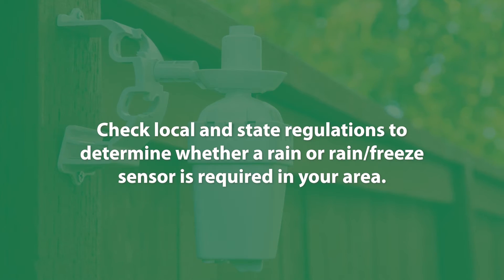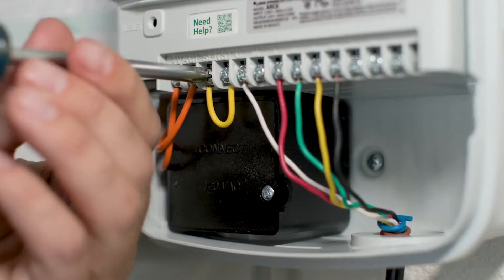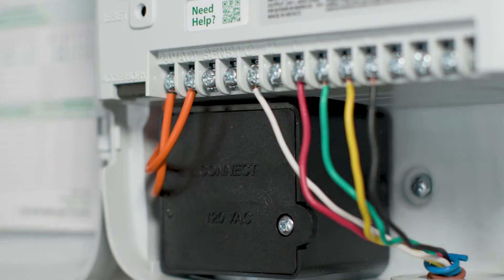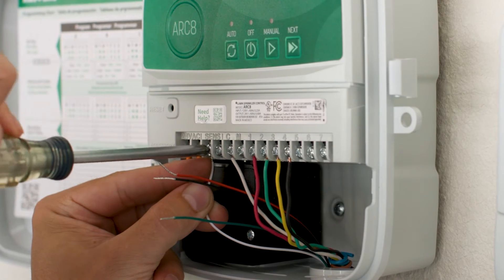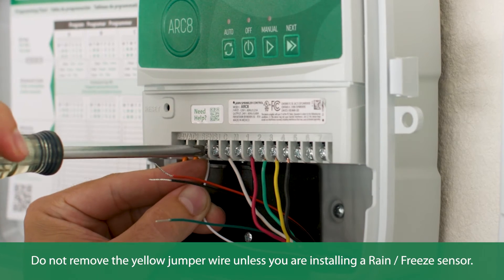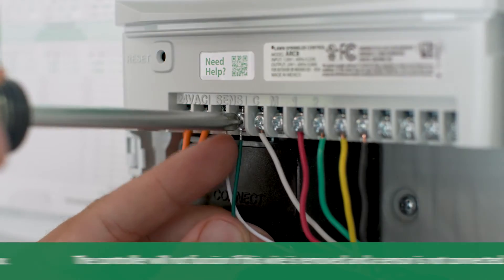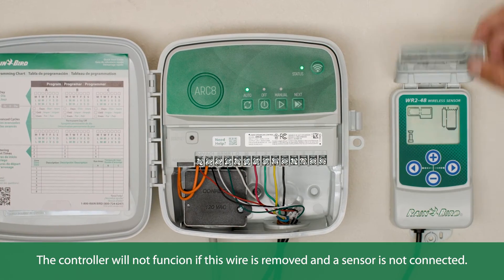Be sure to check with your local and state regulations to determine if a rain or rain freeze sensor is required in your area. To connect a sensor, remove the yellow jumper wire from the SENS terminals on the controller, then connect the two sensor wires to the SENS terminals. Do not remove the yellow jumper wire unless you are installing a rain freeze sensor, as the controller will not function if this wire is removed and a sensor is not connected.